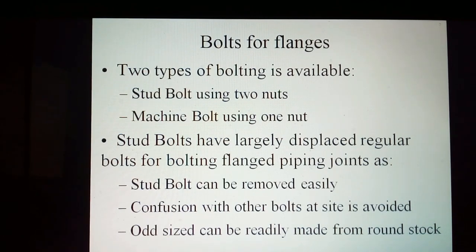ASME B16.5 defines stud bolts for flange classes from 150 to 2500 psi, while it defines machine bolts for class 150 and 300 psi only.